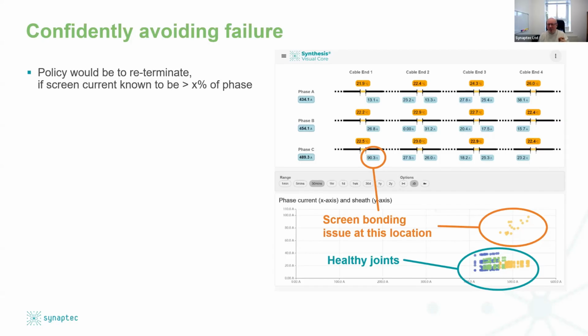I can re-terminate, I can replace some parts, maybe there's a broken path, maybe there's a bad connection, some water ingress. There could be several failures associated with this. But traditionally, it's too expensive to put all the equipment, even partial discharge monitoring, in all of these locations. And in fact, in this example, in a 400 kV double circuit cable system with, I think it was 192 locations, that cost became prohibitive.